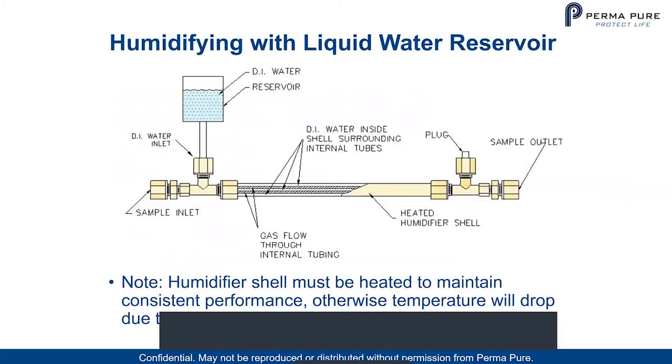Here's humidifying with a liquid water reservoir. This is one way to humidify, though I don't really think it's the best way. The water sits in a reservoir that feeds the humidifier tube, and in this case you have to heat the shell to keep the water at the same temperature. I don't think this has the best performance because it's not always as consistent.